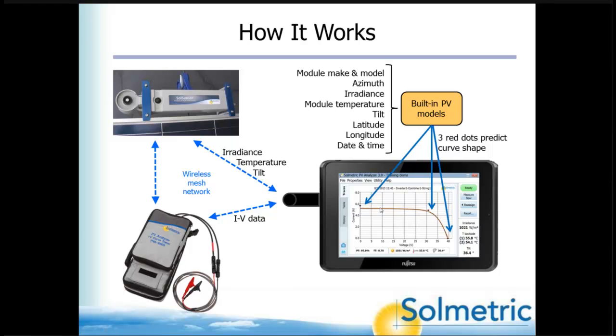There are 3 dots published on the screen to which the measured curve trace is compared. Those 3 dots are generated from an internal PV model, informed by all of the factors listed in parentheses at the top. So it's really nice — you have an actual set of reference dots at the temperature and irradiance at which you're measuring to compare the trace. You don't have to translate the trace down to STC conditions and lose some of the physical insight.